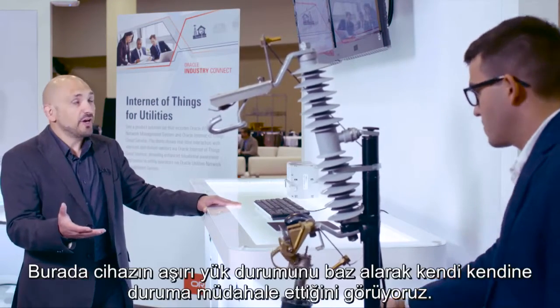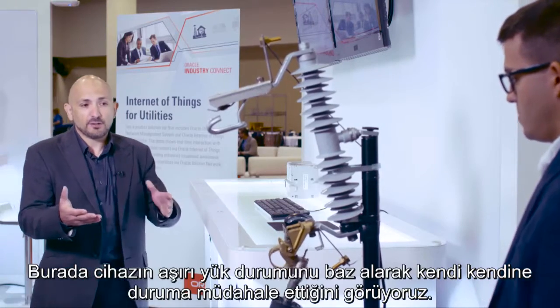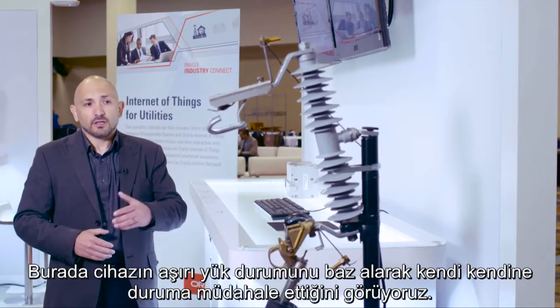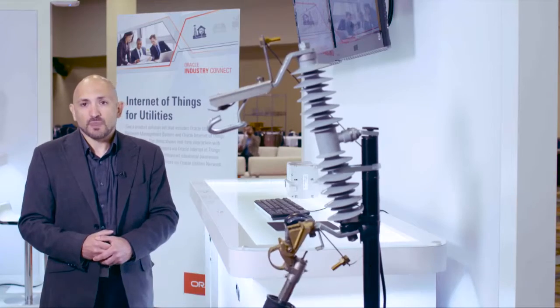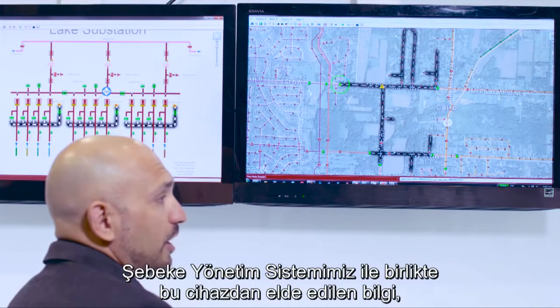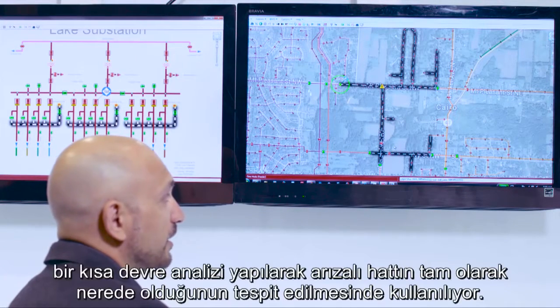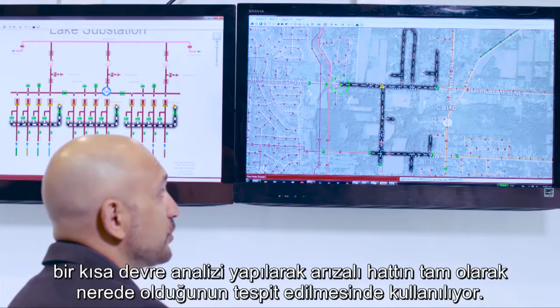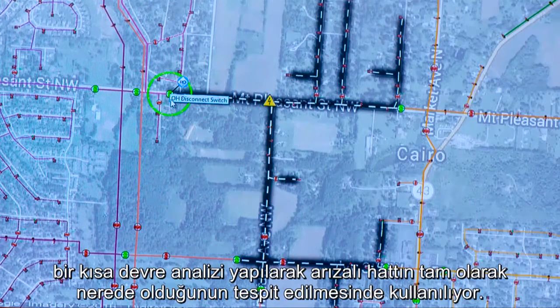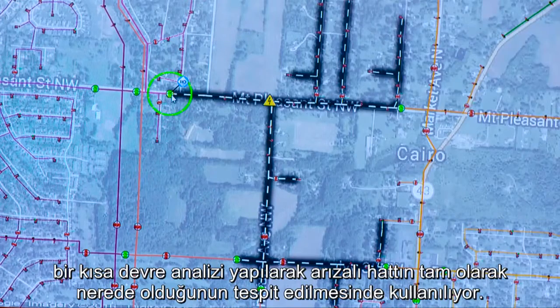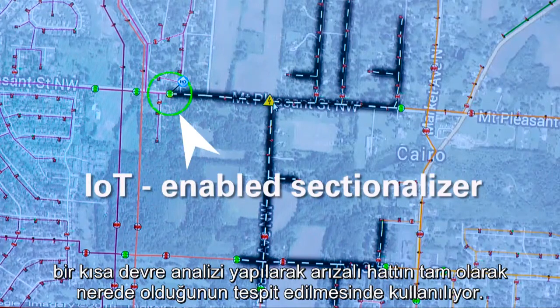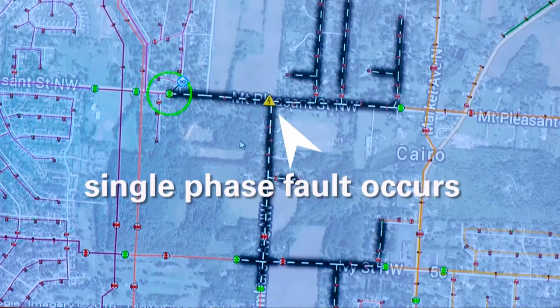So here we saw this device operate autonomously based on an overcurrent condition. And in conjunction with our distribution management system, the information received from this device was used to do a short circuit analysis and pinpoint what it expects the faulted line to be by marking this section as faulted.